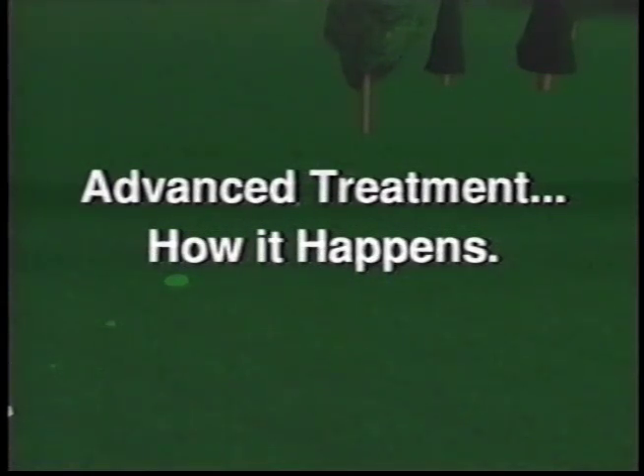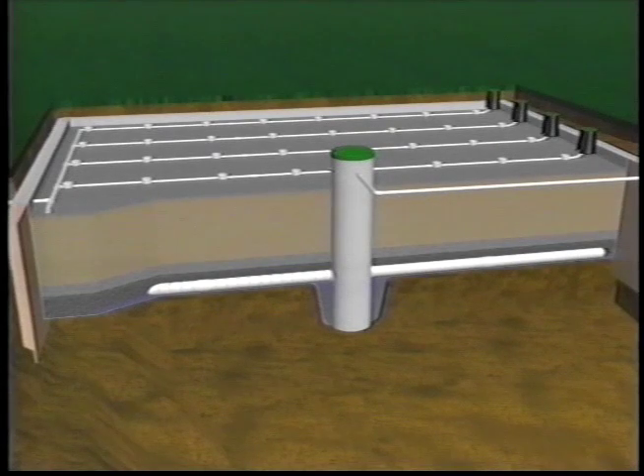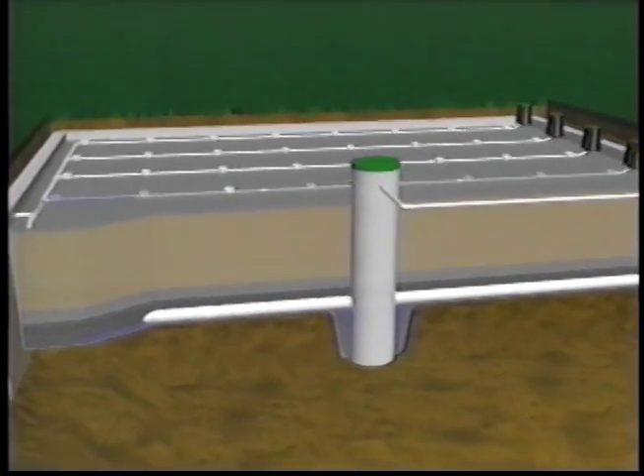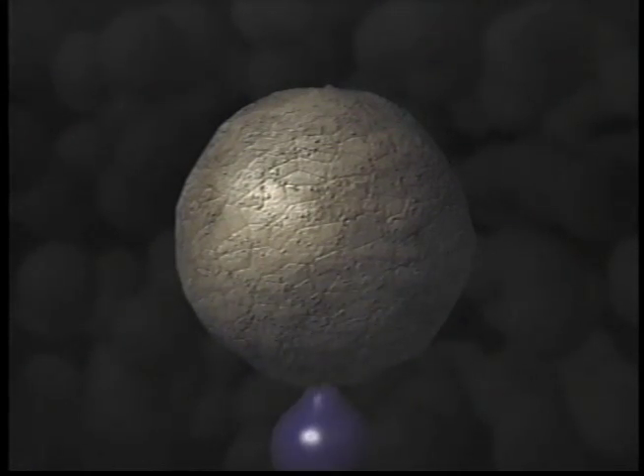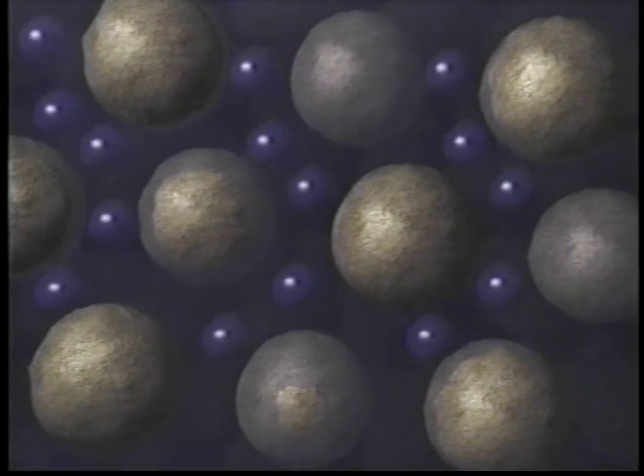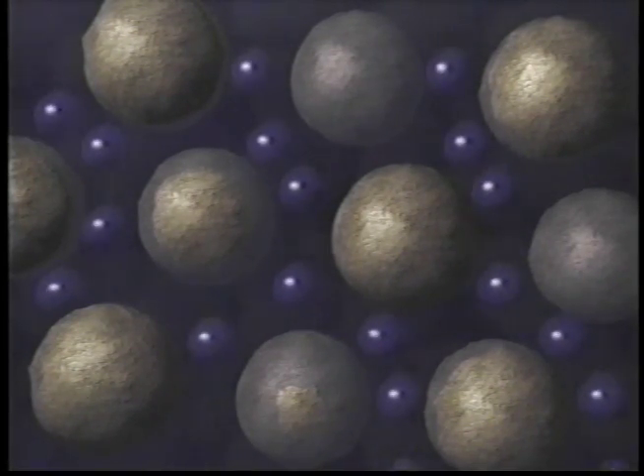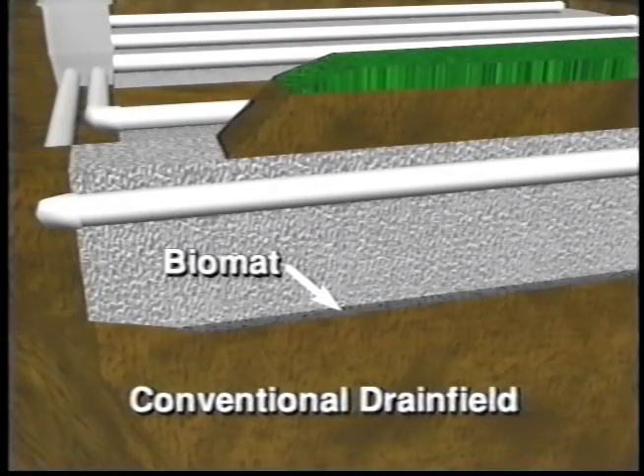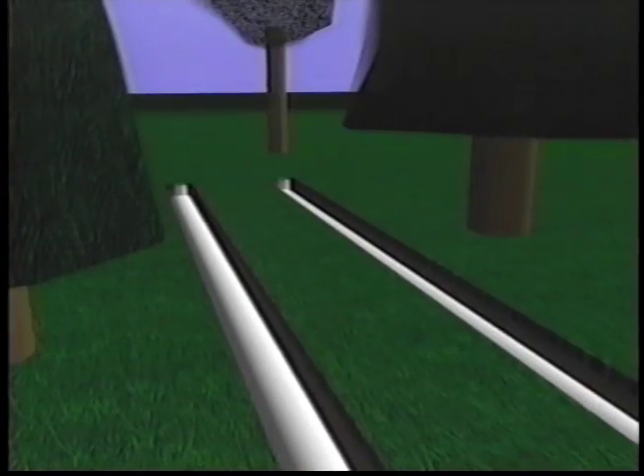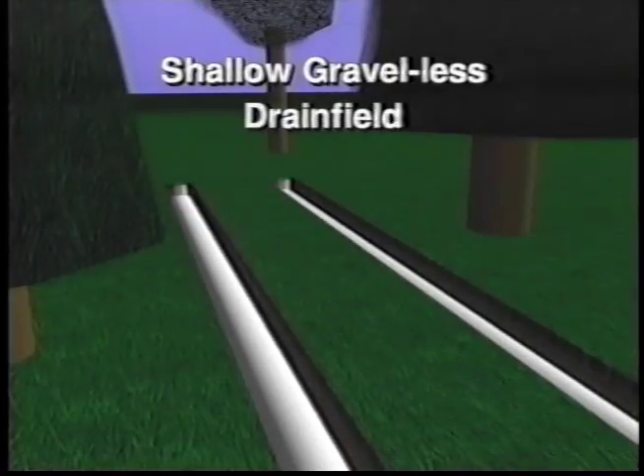How do ISF systems accomplish such a high level of treatment? First of all, an efficient distribution manifold ensures that all — not just part — of a filter bed is involved in the treatment. But the real key to efficiency is microdosing. Small volume doses allow effluent to move slowly around the sand particles, with plenty of time for natural bacterial reduction to take place. By contrast, large doses that flood the system cause effluent to percolate so rapidly through the sand that there's not enough contact time for adequate treatment. The effluent from an ISF system has received such advanced treatment that it's often hard to distinguish from tap water. That clear effluent also doesn't form a restrictive biomat like the one that occurs in conventional septic tank drain fields. Therefore, ISF effluent can be discharged safely into a short, shallow, gravelless drain field.